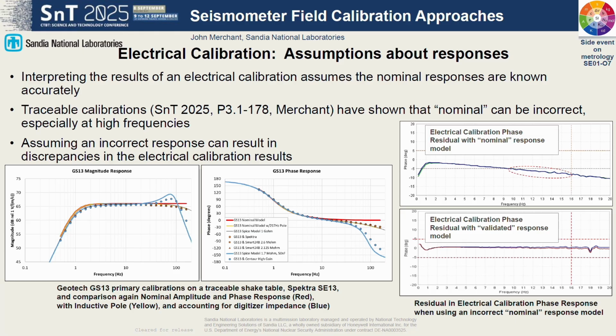But ultimately, if you do an electrical calibration with the wrong response model, you're going to be mathematically removing what you believe to be the responses for the seismometer and the calibrator. And if you assume poorly, you'll be left with a residual that's non-unity, non-zero. And so you can see these two plots on the right now. The topmost one is just using the generic seismometer nominal model. And you can see that there's a phase residual. And I've highlighted the section where it actually exceeds the 5-degree requirement for IMS purposes. If we use a model that has additional poles that were left out by the manufacturer, then they correctly account for that residual, and we're left showing that things are right. So the takeaway, I guess, would be that the electrical calibration is only as good as the assumptions that you made before you did it.